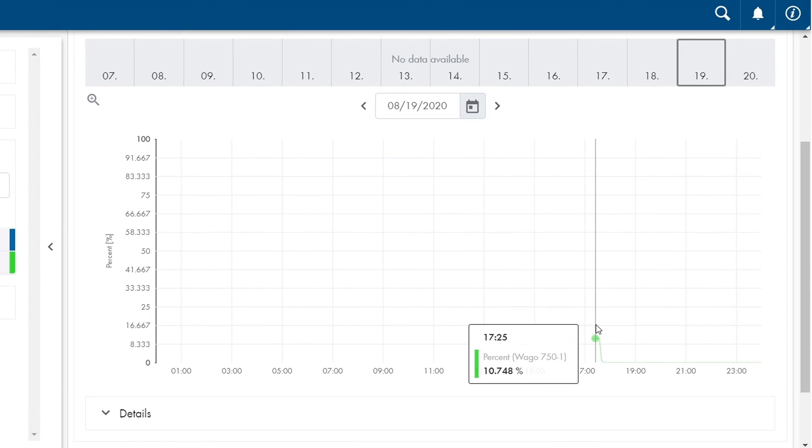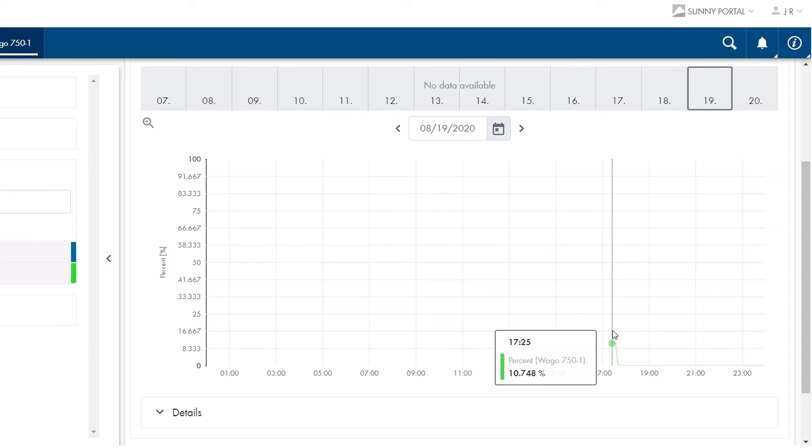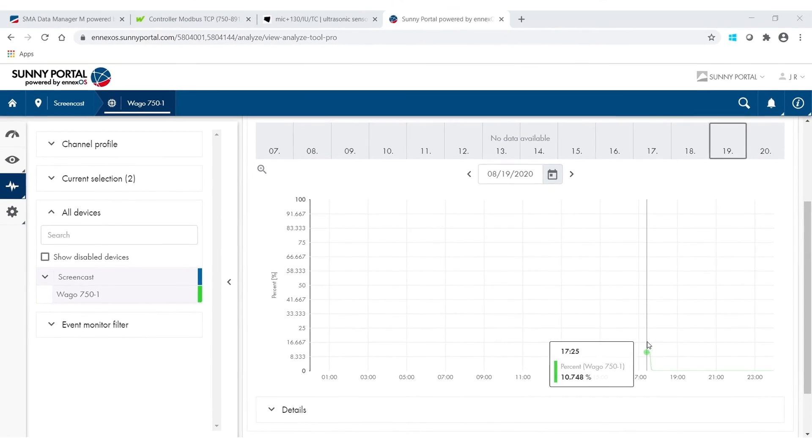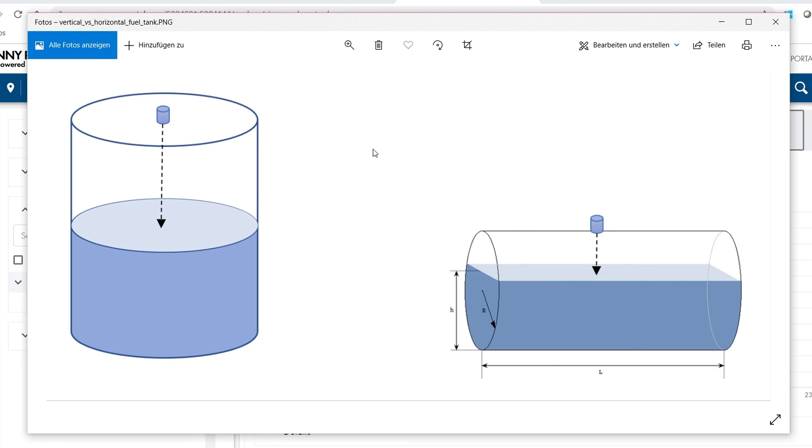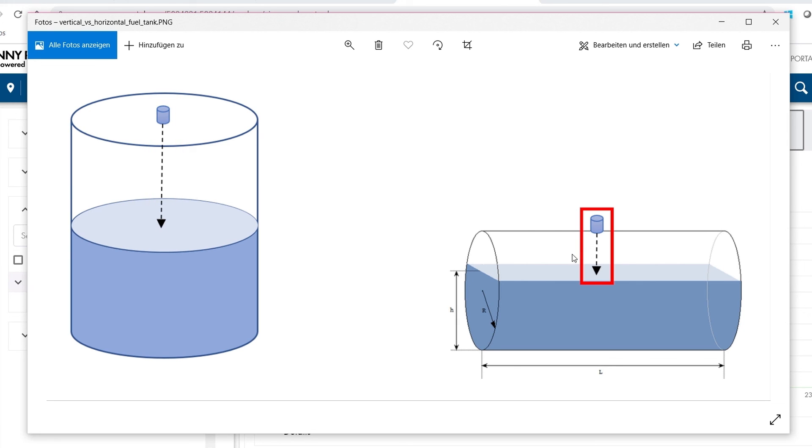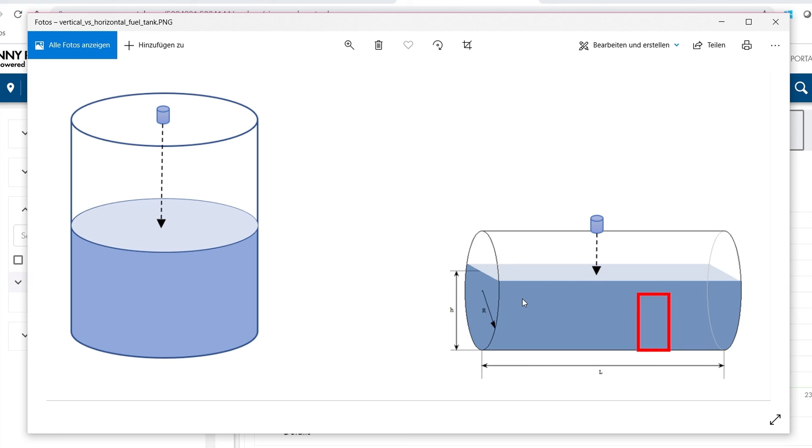Now before I go, just one final hint concerning vertical versus horizontal fuel tanks. The ultrasonic sensor can only measure the actual height of the fuel tank level as I hope you can see in this sketch. Therefore the percentage value can only be accurate in a vertical fuel tank, whereas the percentage value in a horizontal fuel tank can only be completely accurate at 100 percent, 50 percent and 0 percent.